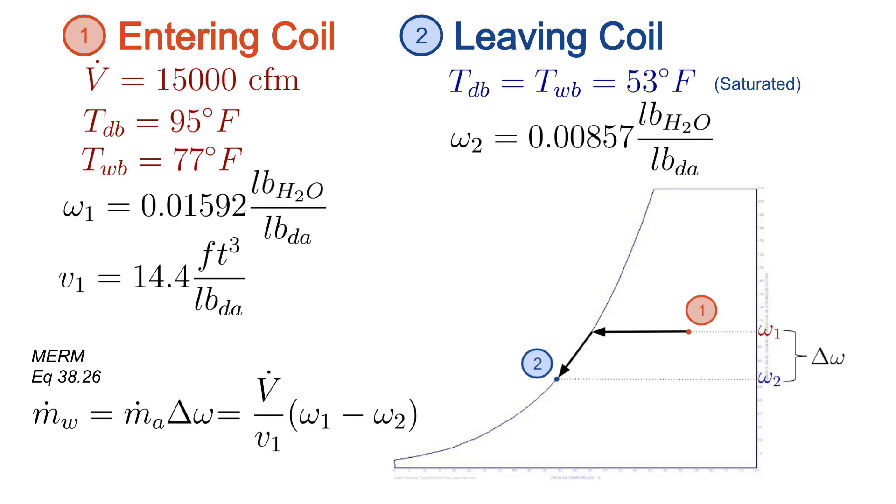Also, we don't actually know what the mass flow rate of air is, but we do know the volume flow rate, which we can divide by the specific volume for state 1. So we'll rearrange the equation as shown here. And we can also expand the delta between the humidity ratios as shown. So let's jump to a clean slide and plug it all in.